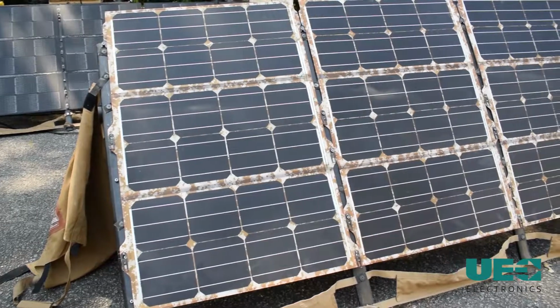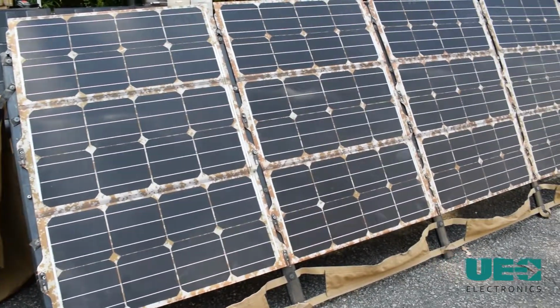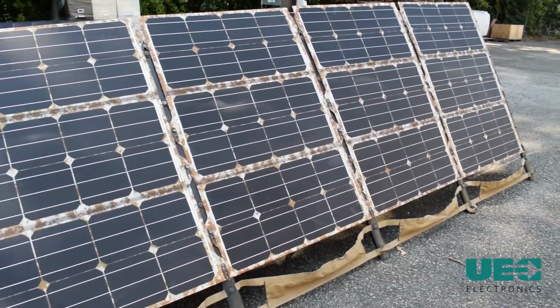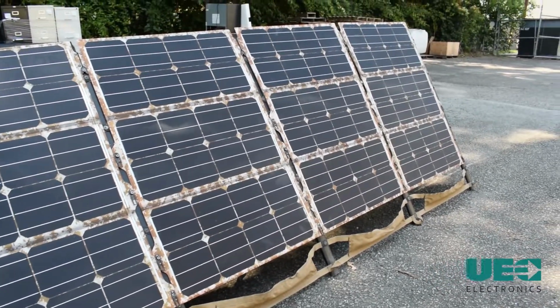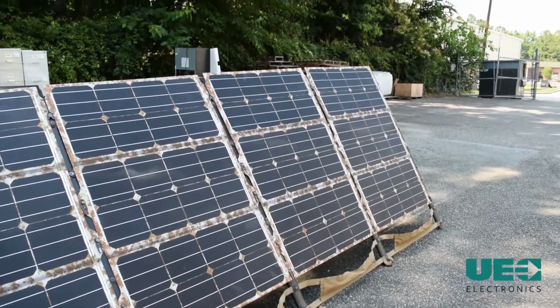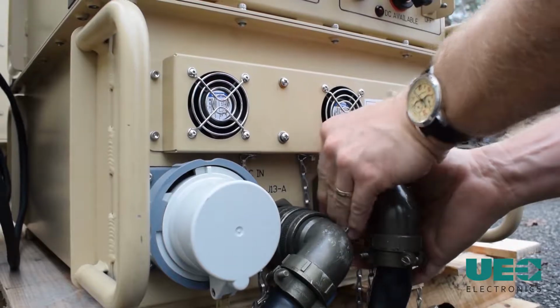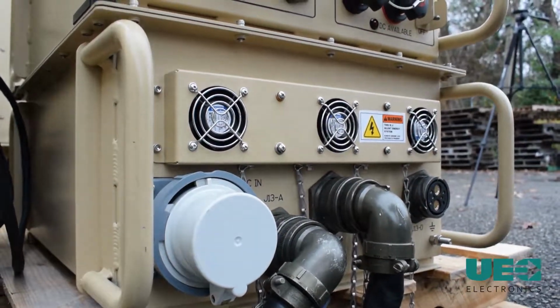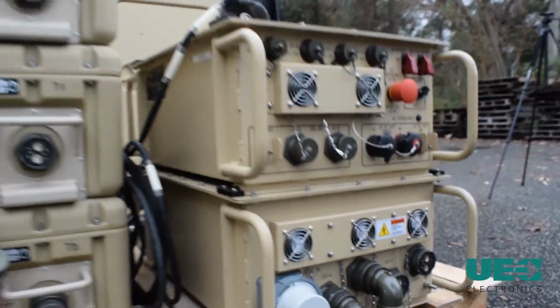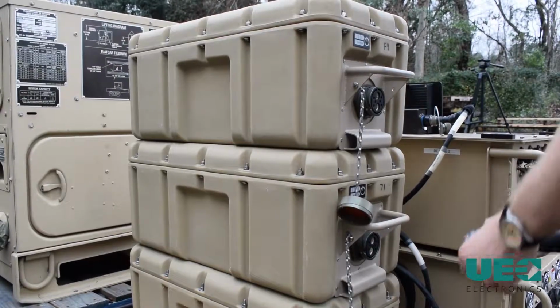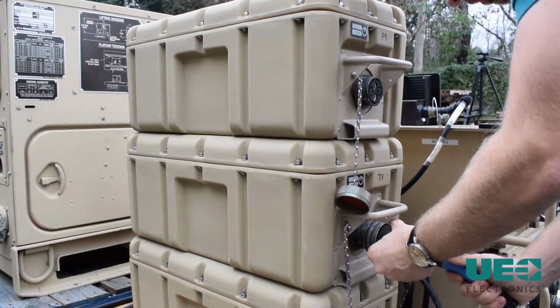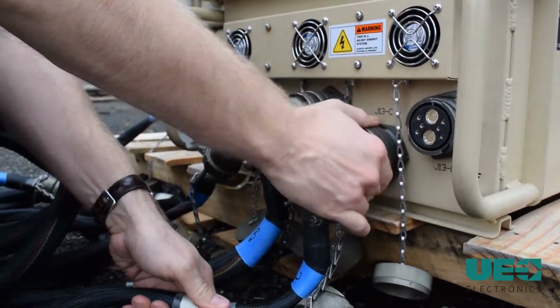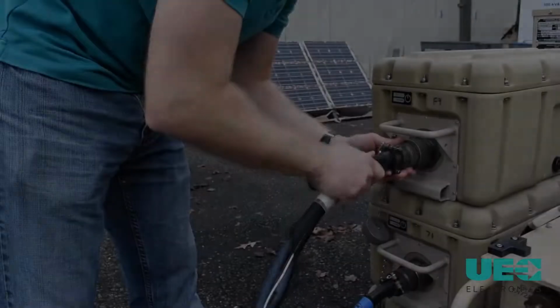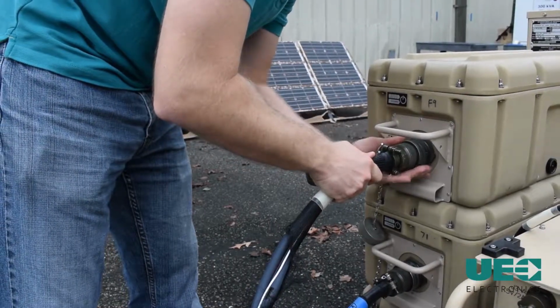Deploy the solar arrays and connect the arrays to the solar input cable. Then connect the cable to the solar input receptacle on the DC PDU. The next step is to connect all of the major components of the system using DC link cables. Connect all 3 batteries to the DC PDU. If additional batteries are available, 2 or more can be connected to the DC PDU.